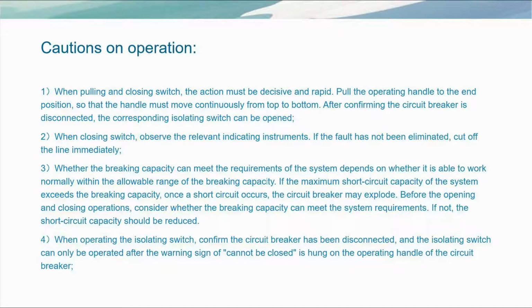Cautions on operation. 1. When pulling and closing switch, the action must be decisive and rapid. Pull the operating handle to the end position, so that the handle must move continuously from top to bottom. After confirming the circuit breaker is disconnected, the corresponding isolating switch can be opened. 2. When closing switch, observe the relevant indicating instruments. If the fault has not been eliminated, cut off the line immediately.